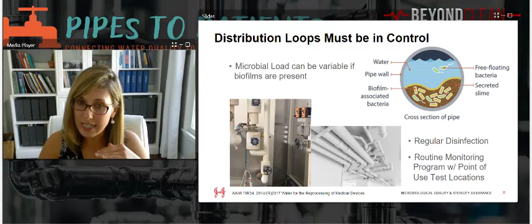So anywhere you see something like this, there might be a dead leg in your system. See this little end there labeled dead end? That's problematic because it means there is a stopping point where water is not flowing, where microorganisms can grow, where a biofilm can develop, which means you're getting that increased growth over time.